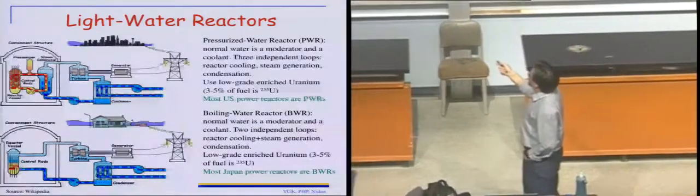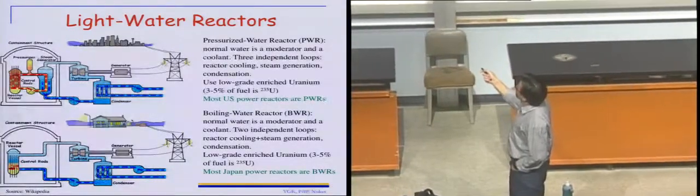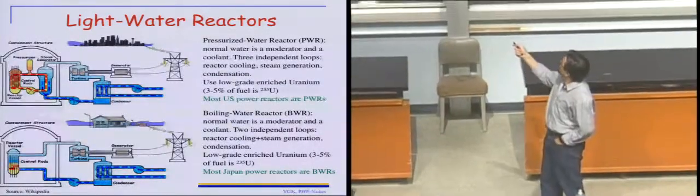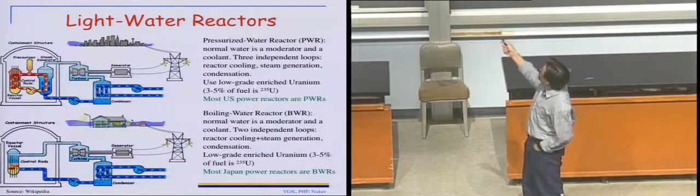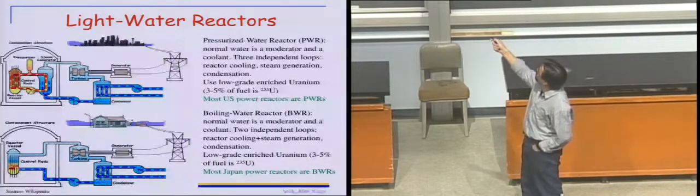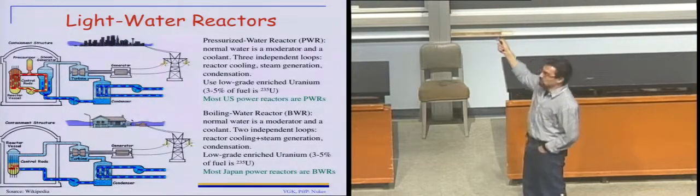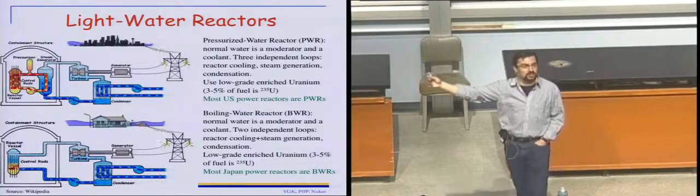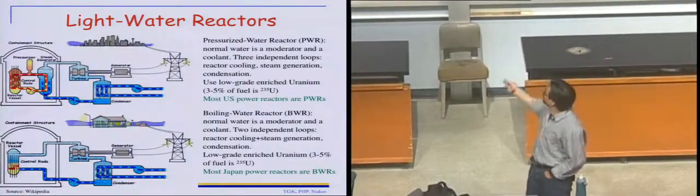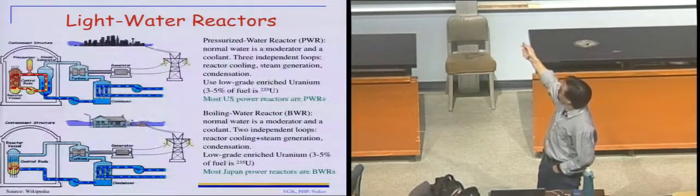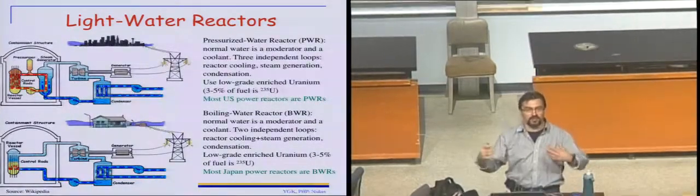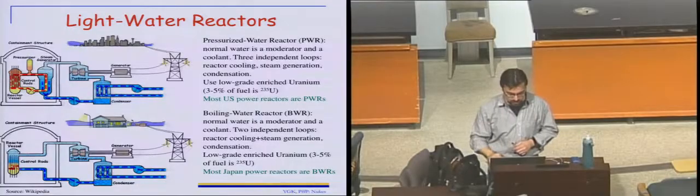Plus also, a leak in the containment vessel in the boiling water design can potentially contaminate; this loop is one step closer to the condenser loop that's potentially connected to the environment. So you have to make sure that there are no leaks between this loop and this loop. In the pressurized design, there's one extra loop in between, and so that's possibly a little bit safer.